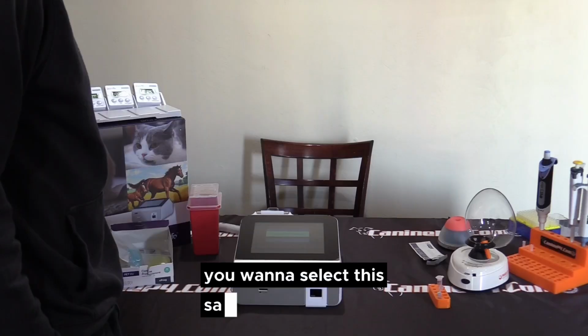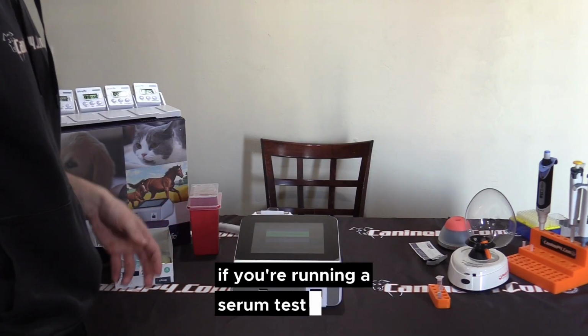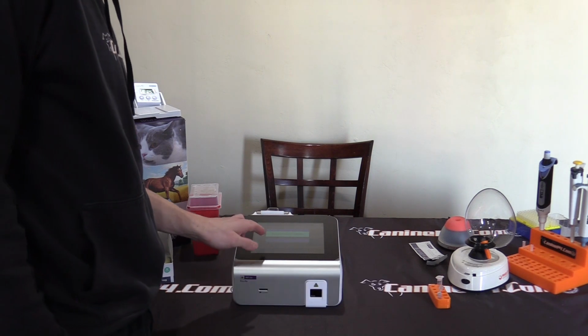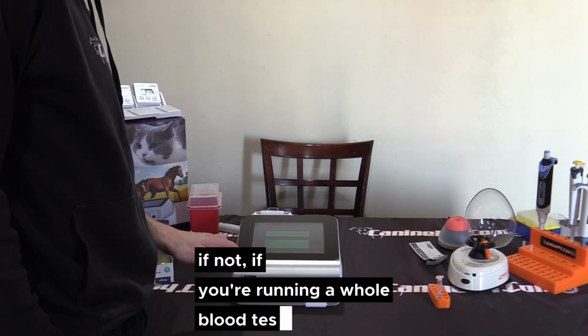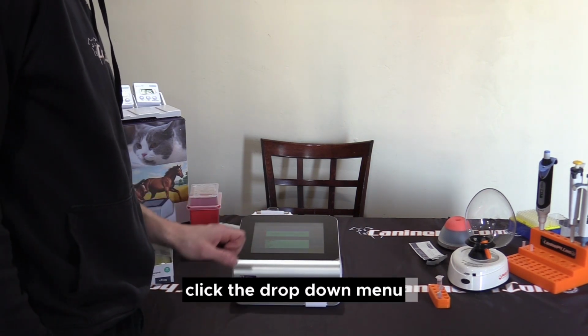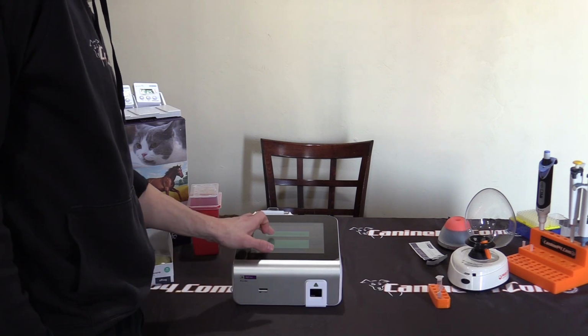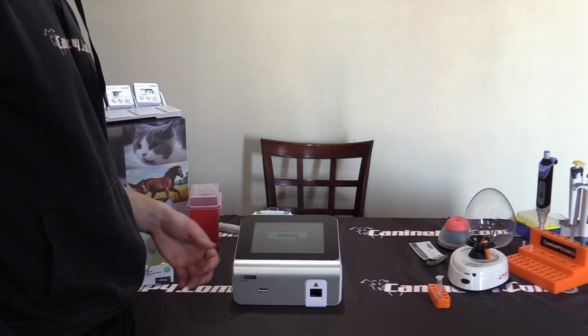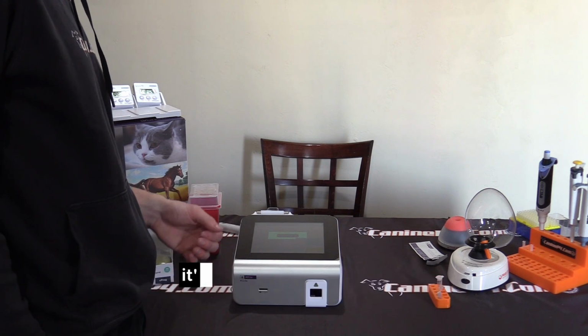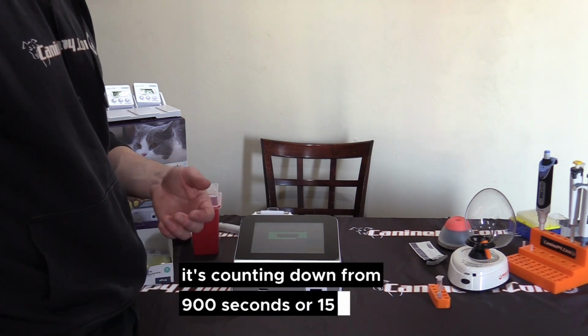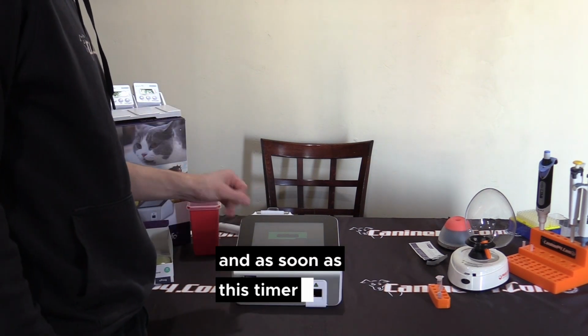Start Test. It's going to ask you if you are sure you want to select this sample type. If you're running a serum test, you can click OK, confirm. If not, if you're running a whole blood test, click the drop-down menu, select whatever sample you're running, and then click Confirm. And now the incubation process started. It's counting down from 900 seconds or 15 minutes. And as soon as this timer is up, we'll have a result.